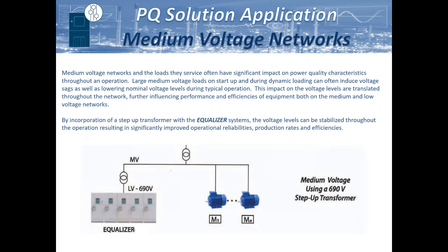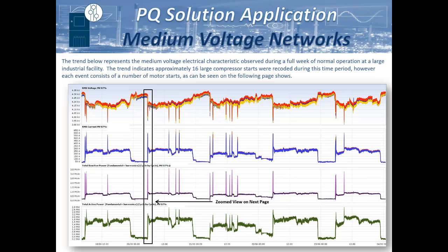We also do medium voltage applications as well. We design the system based on either a 600 volt or 690 volt platform, and then utilize a step-up transformer to bring it up to whatever voltage is necessary, whether that's 4160 or other levels. We've actually done work for utilities, at the substation level and regional distribution, to stabilize the network from wide customer and client load demand variations.